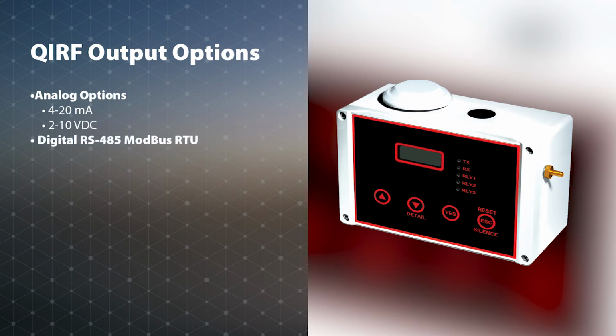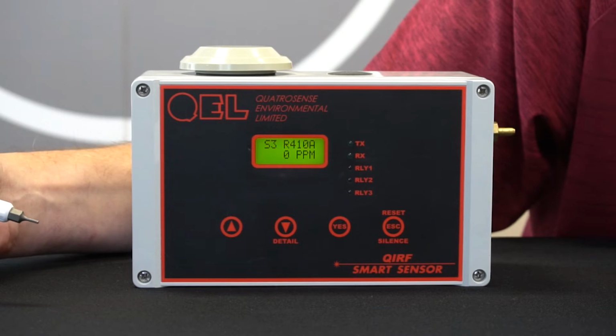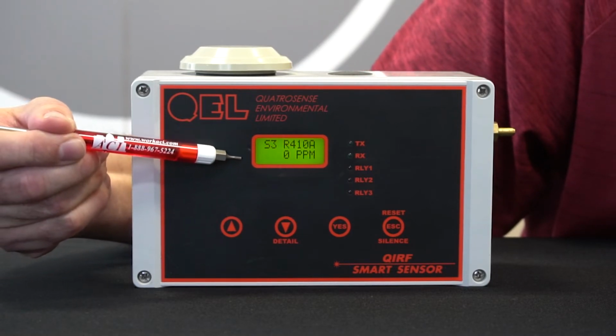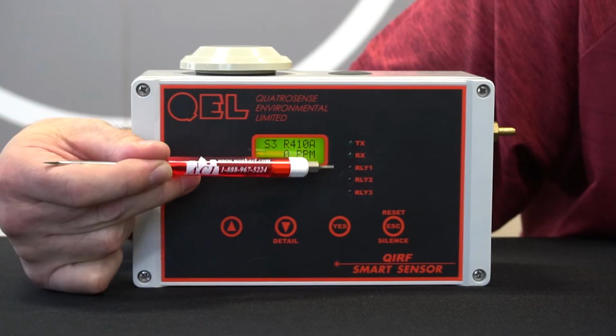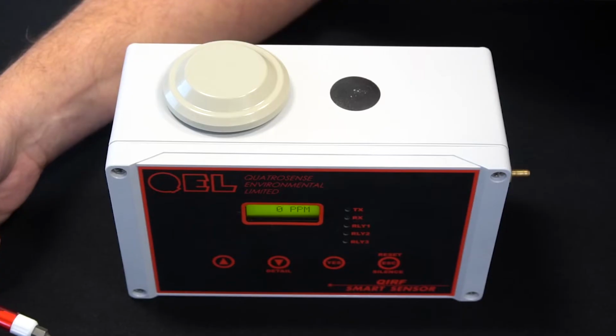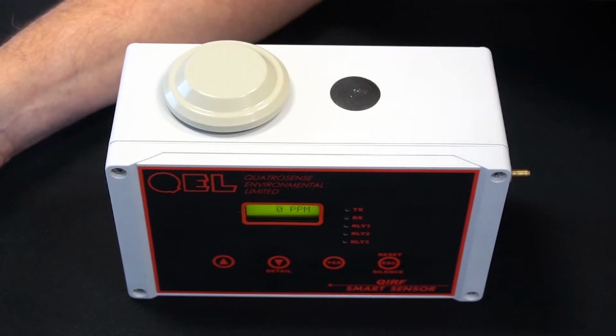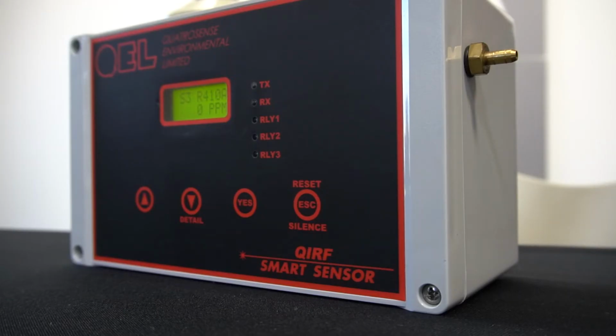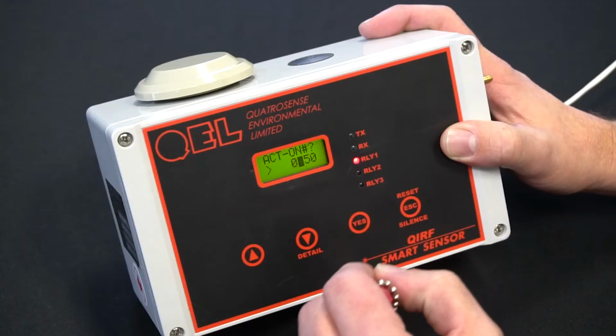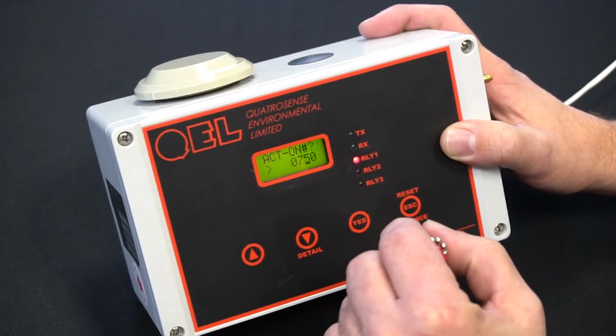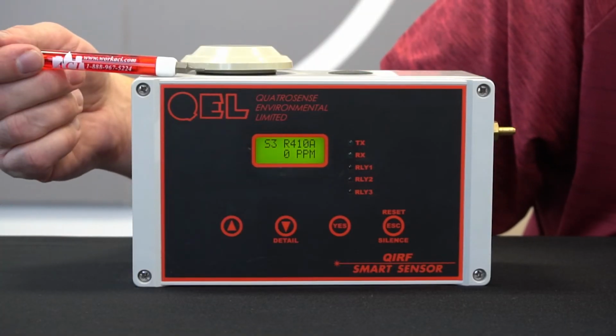The QIRF has analog output options of 4 to 20 milliamps or 2 to 10 volts DC, as well as digital RS485 Modbus RTU or Optimix protocol for QEL controllers. Standard features on the QIRF include 3 onboard single-pole double-throw Form C relays, which can be individually programmed, a 2x8 character backlit display, 5 status LEDs to monitor communications and relay status, an 80 decibel buzzer with 3 programmable tones, 14-year sensor life, 3% accuracy, 7,500 square foot coverage area, magnetic keypads, and a NEMA 4X enclosure.